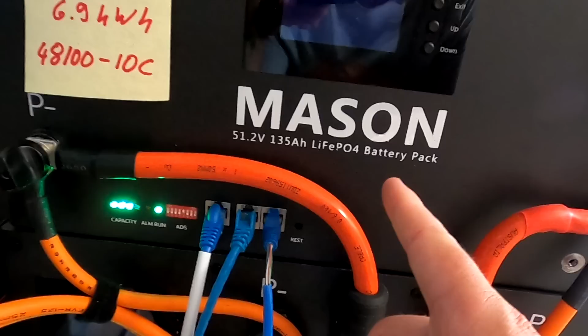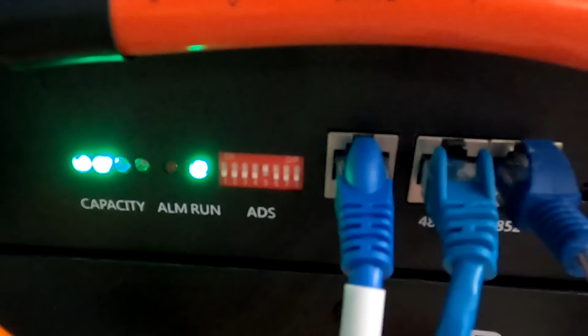I cannot access the top battery configuration of the BMS anymore, because this combination of dip switches does not exist for RS485 communication. So there's no way to access the master battery of your Seplos battery banks if you have more than one in parallel. One bank, totally fine. Two banks or more, you cannot access the master battery anymore.